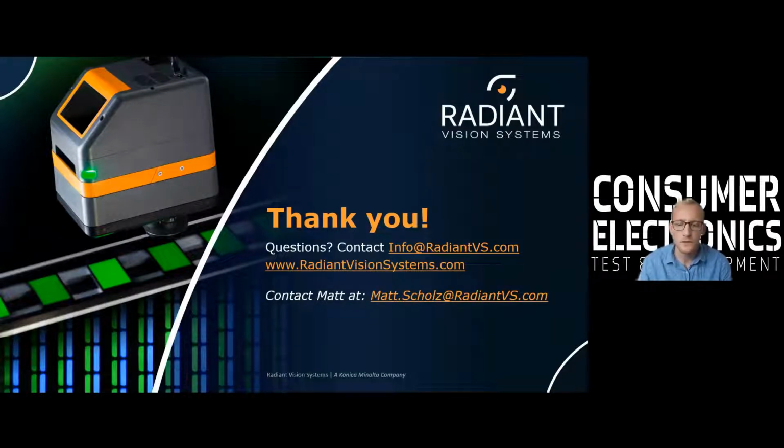Okay. That's how angular dependent are your imaging photometers when measuring that luminance and or color for display? Yeah, that's a question that people ask us all the time. And that's a really great question, because many people probably don't know that we go through something called a linearity scaling calibration and a flat field calibration. Both of these calibrations help us with the orientation of the camera and the angular dependencies of the device under test back to the camera lens and the sensor itself to help mitigate the angular degradation that many people might see with uncalibrated systems.